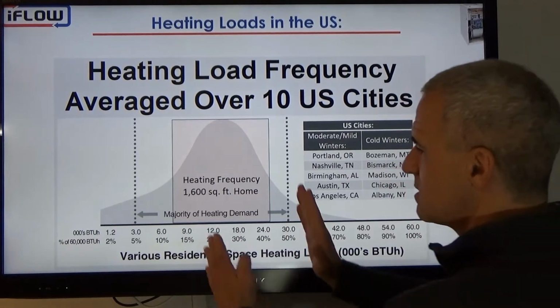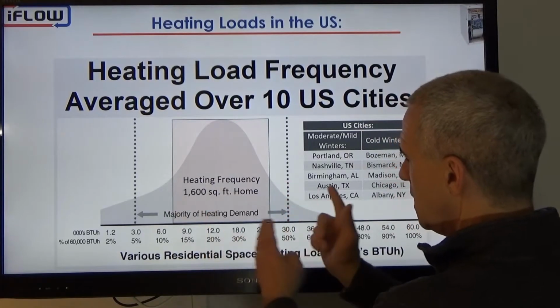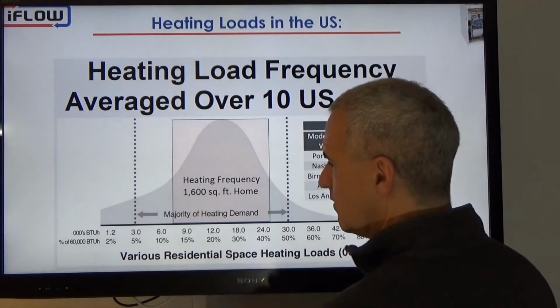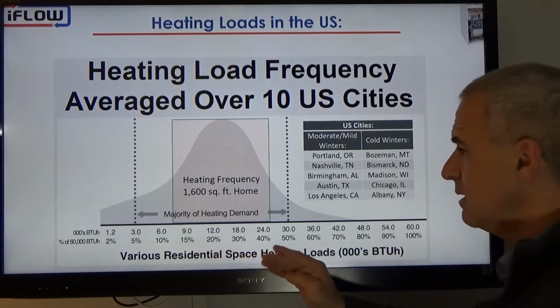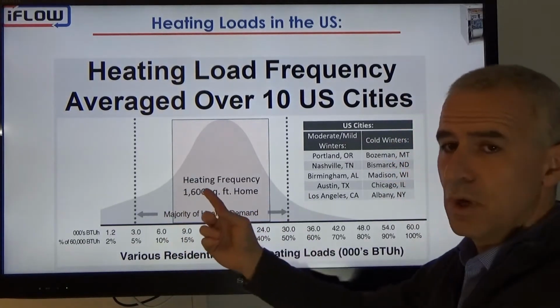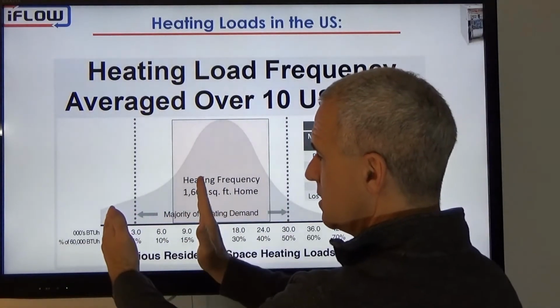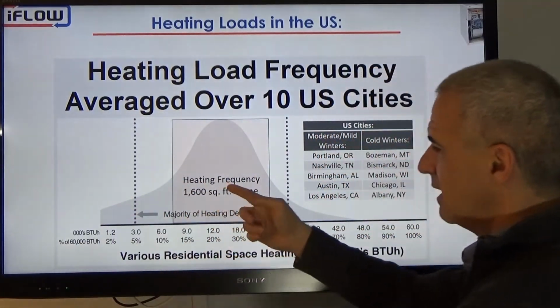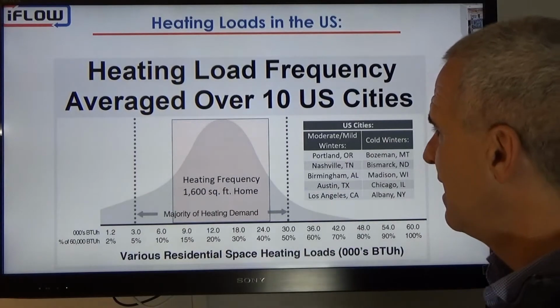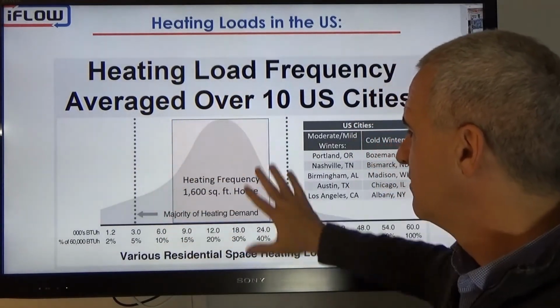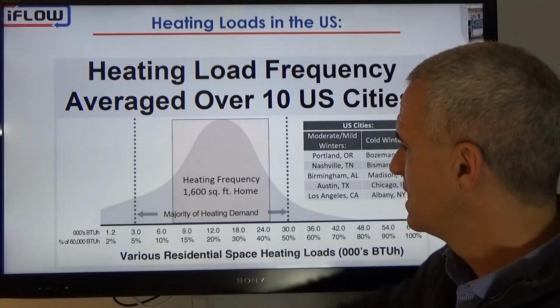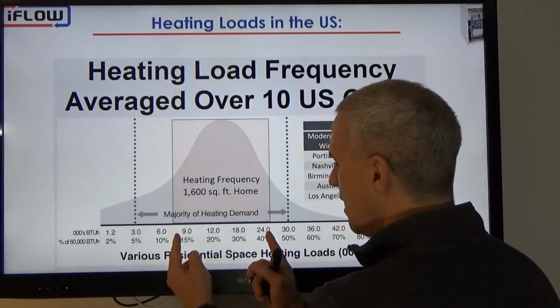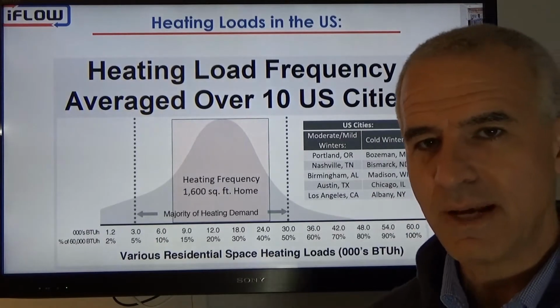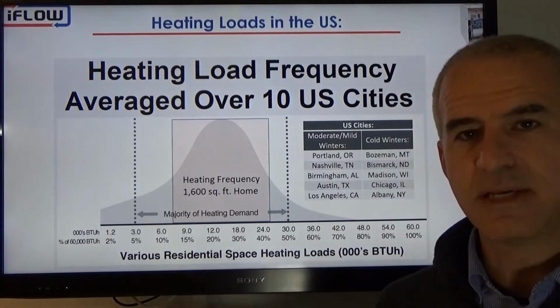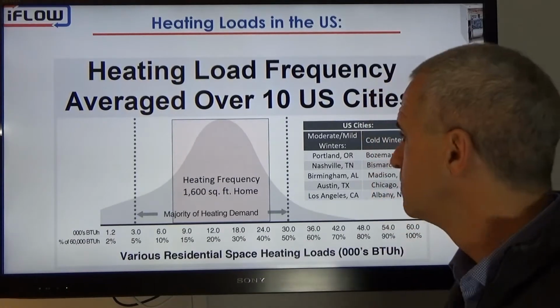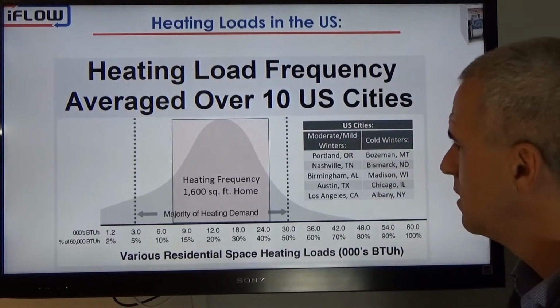So in the colder areas, the curve might shift a little bit to the right. In the warmer areas, a little bit to the left. If it's a smaller than 1,600 square foot house, a little bit to the left. Bigger house, a little bit to the right. So all to say, this is representative of a number of different areas, all averaged together, but it shows that the heating loads are much, much lower than we expect them to be. Nowhere near 60 or 80 or 100,000 BTUs, right? And this is in the US.